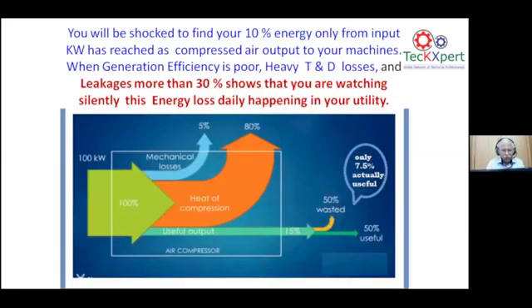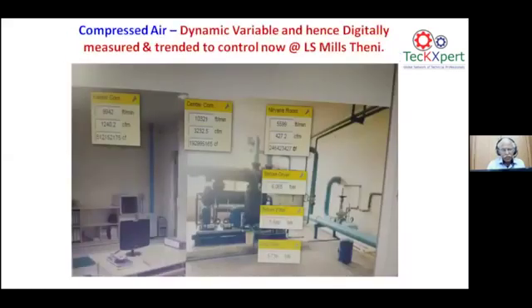If you find the compressor is losing more, not only on the mechanical side, there is the heat of compression. This is where almost 80% of the loss is happening. So the heat of compression is seen throughout the compressor house and depends on how the compressor house is maintained. Then comes the useful output, which is around 15%, and there also 50% is getting lost at the load end. If you see, this is a case study we have done at LS Mills at Theni. They have maintained an excellent study. They have done it totally digitally. All the flow rates, everything is digitalized. What is the velocity of the compressed air? What is the CFM?